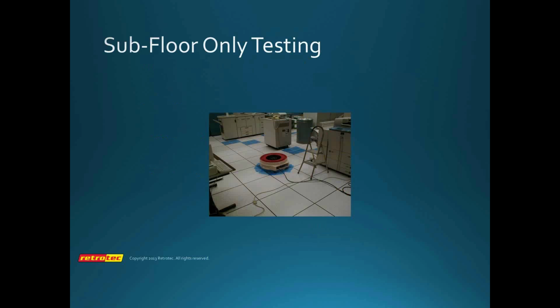The same technique can also be used for subfloor only testing. So here we have a fan blowing in the subfloor. In this case, we would be pressurizing the room so that the pressure across what we call the walk-down floor would be 0. You notice in this picture that we have the perforated tiles covered with a grill mask material that seals them off. So this enables us to measure the below floor leakage area.